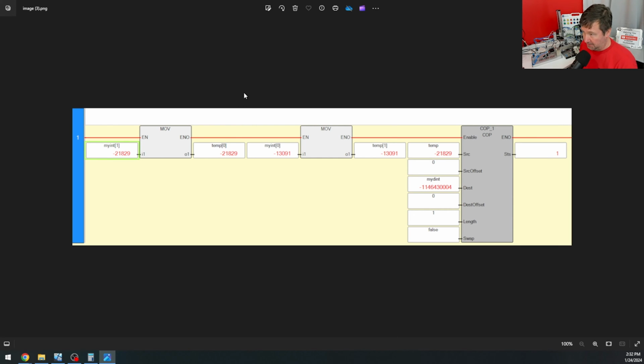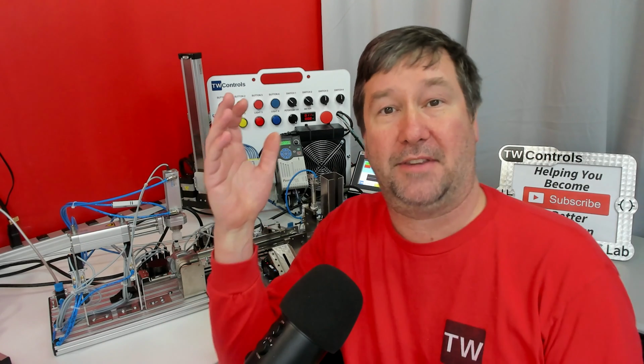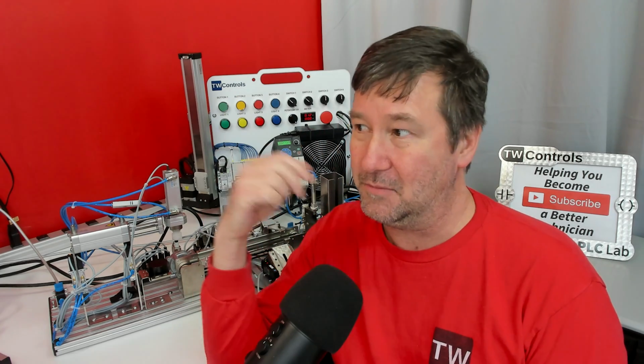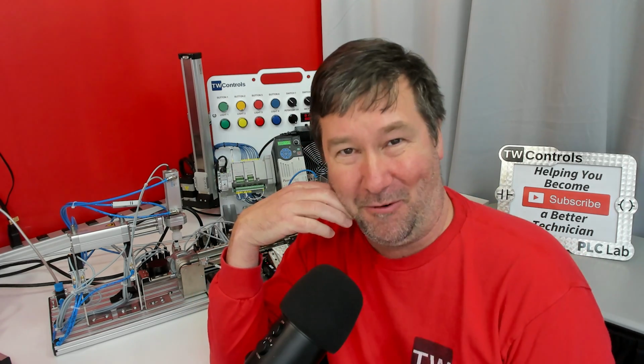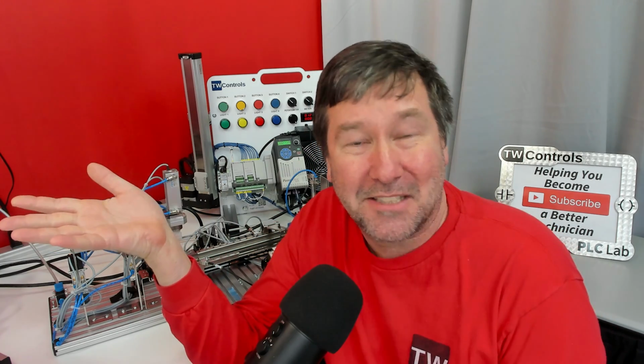I do have to thank Rockwell Tech Support for helping me understand this problem and come up with this. What they are doing is taking my int 1 and putting it in 0, and then my int 0 and putting it in 1. So they are swapping those 16 bits manually and then doing the copy instruction. And that does combine them. I've shared that with quite a few of you, and you absolutely reamed me for the solution. But it does work if we need one.